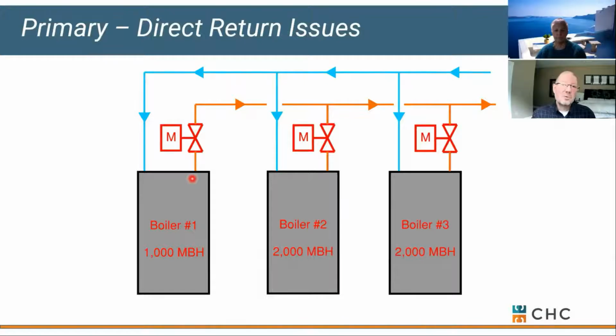Now, just to throw a wrench in the works, let's say we forget all this. We get all excited. We sell some high efficient condensing boilers, and you forget this little talk. And we pipe them direct return, or the contractor does, or us as the rep forgets to catch that little tick mark when we do a job walk. Let's just run through a scenario of direct return piping, okay, and the effects it has on our equipment.